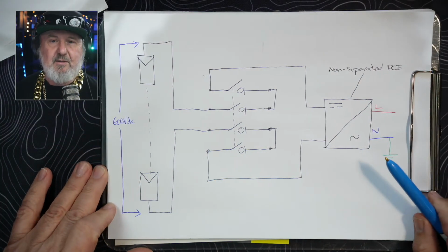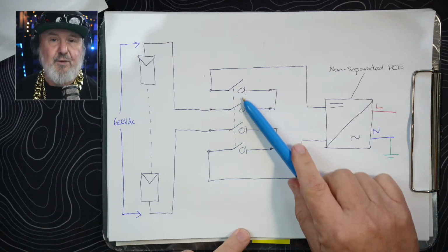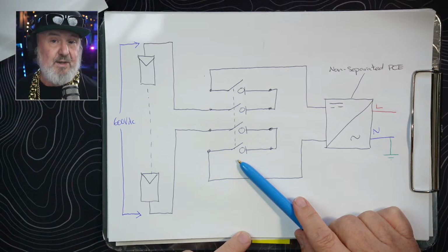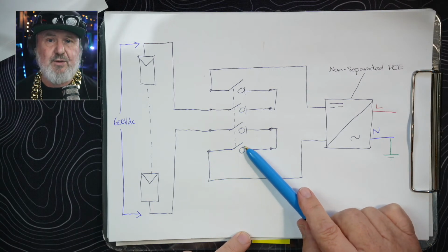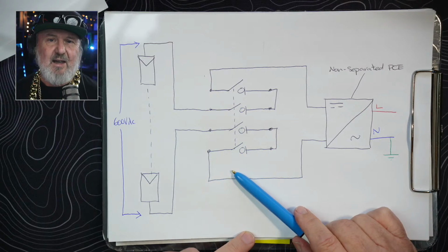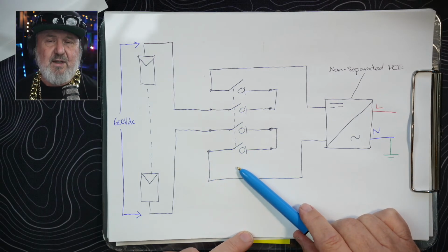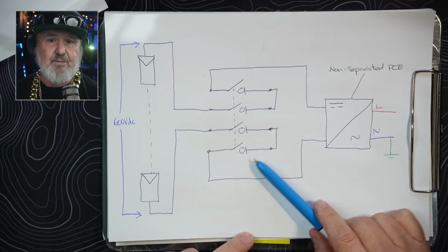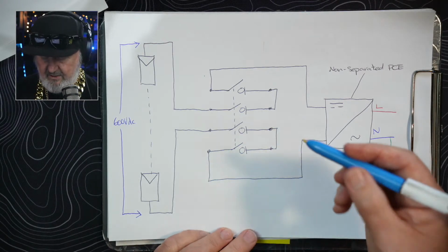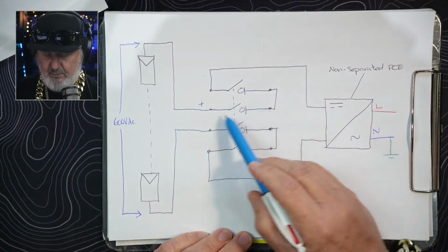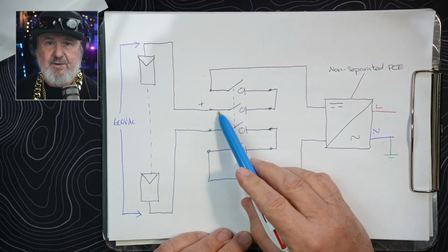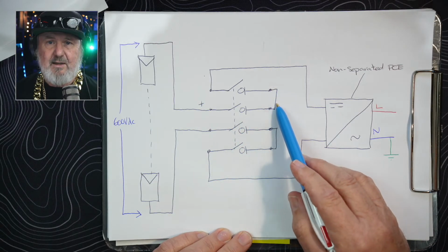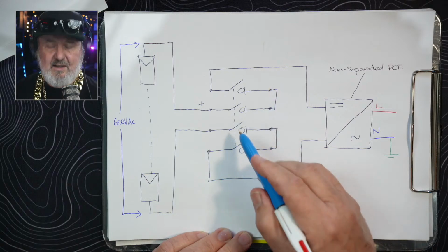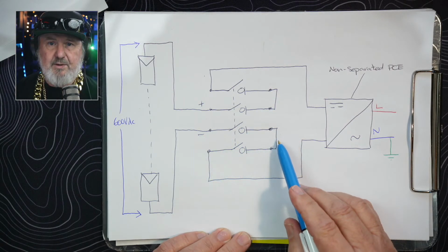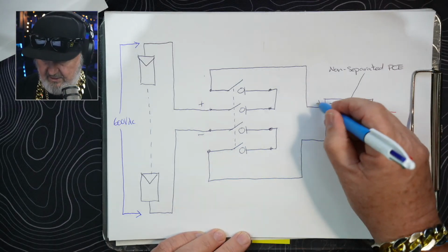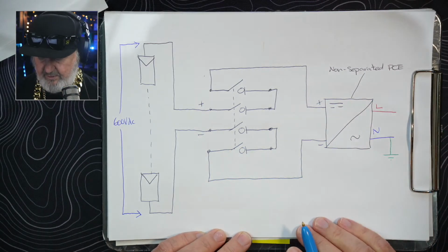Okay, so now I've drawn an array with a 4-poled DC switch, or it could be a circuit breaker. Of course, the symbol's different for a circuit breaker. It'd have a cross there instead of a circle. But this is a very common arrangement for a DC isolator, to have multiple poles. And you'll notice that on the positive side, we've got 2 poles in series, and we put a little link in here to join them together in series. And then on the negative side, we've also got 2 poles in series. All very good there. And so that's the input to the non-separated inverter.